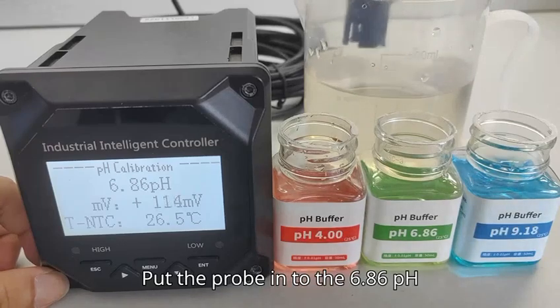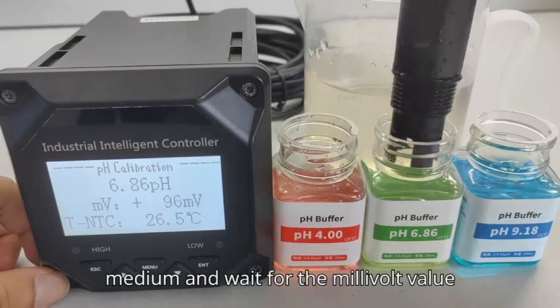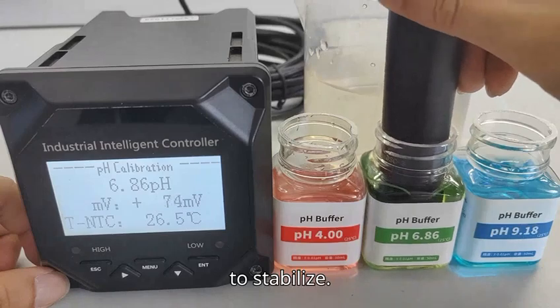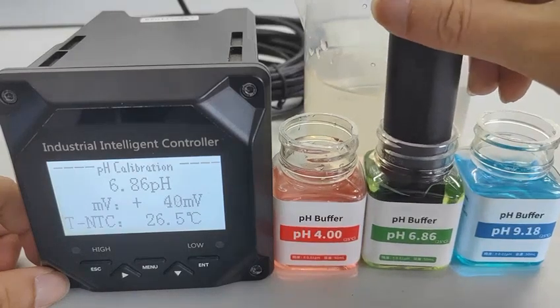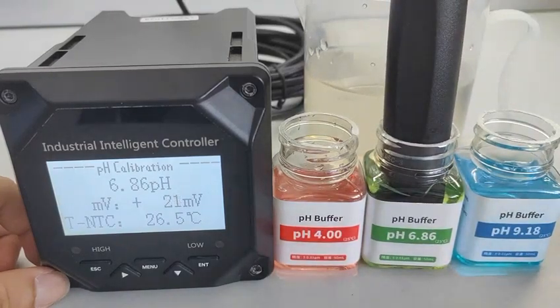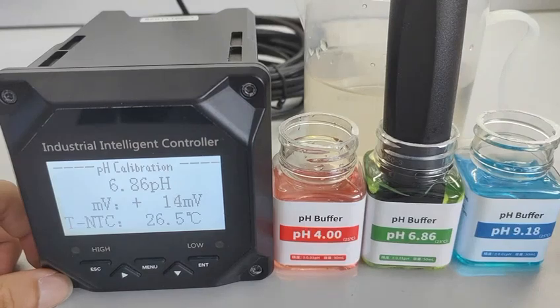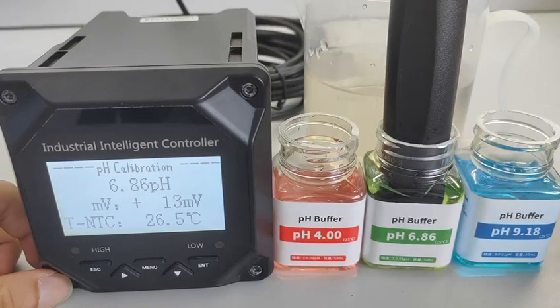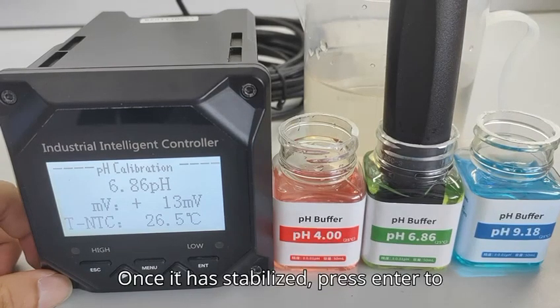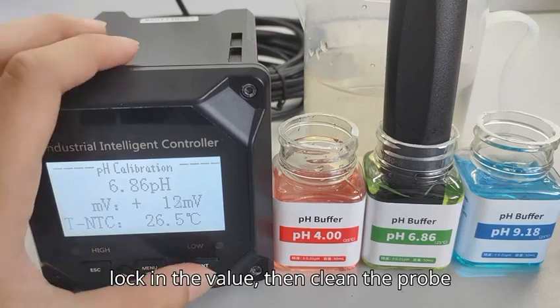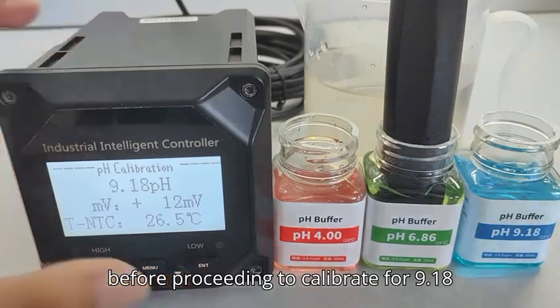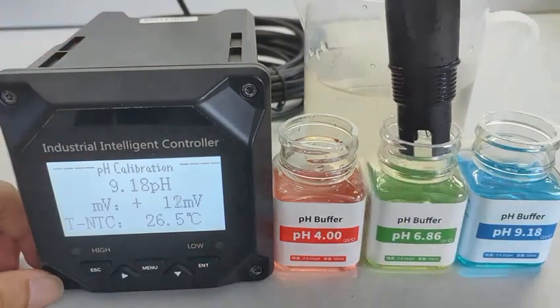Put the probe into the 6.86 pH medium and wait for the millivolt value to stabilize. Once it has stabilized, press enter to lock in the value, then clean the probe before proceeding to calibrate for 9.18 pH.